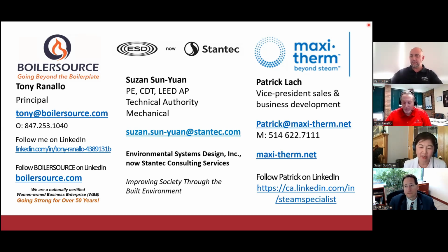So converting from steam, with a future maybe of low temp heating hot water. One thing I would like to remind is that a couple of the projects in our office are facing that. Some of the buildings on the campus utilize steam currently, and there's a consideration to switch away from the steam into condensing boilers actually.